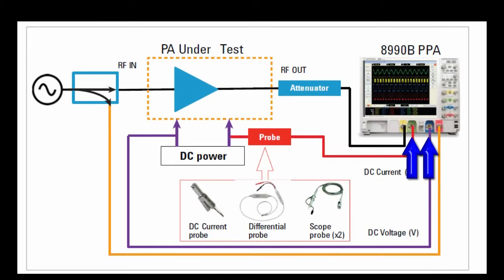The 8990B's analog channel 2 and 3 are used to measure the DC power channeled into the power amplifier. The DC power consists of voltage and current supply to the power amplifier.